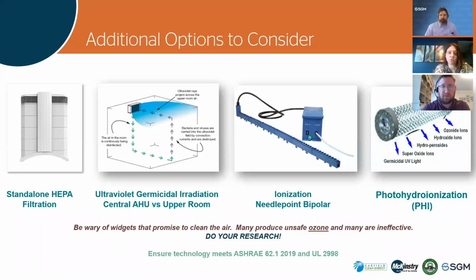And then the next two options are ionization technologies. And while they're not new, they're newly being adopted in the marketplace. And there's some caution we would advise here, as well as ASHRAE, is essentially their position is that these look promising, but we need more data. And then one last note here, just be wary of widgets that just say they clean the air. You want to make sure they're safe and don't produce ozone. Yeah, note on the air cleaning devices, they must meet ASHRAE 62.1 2019. And that requires that they be listed and labeled in accordance with UL 2998.